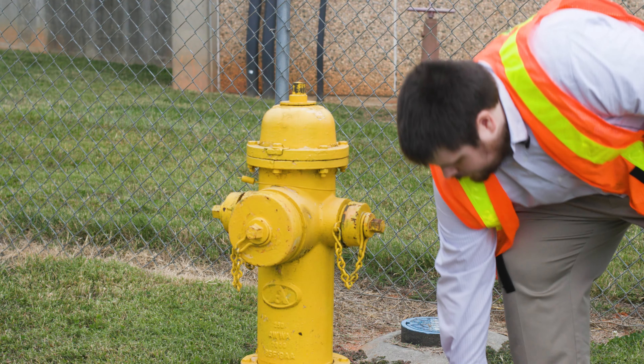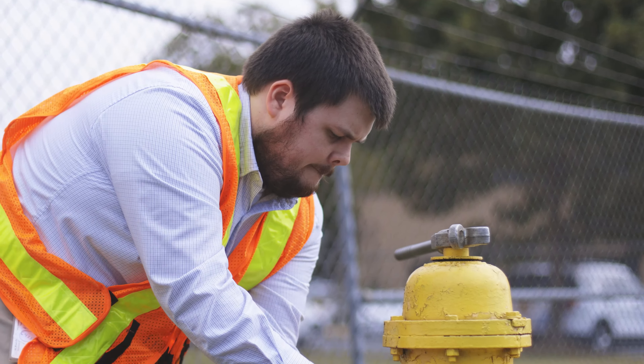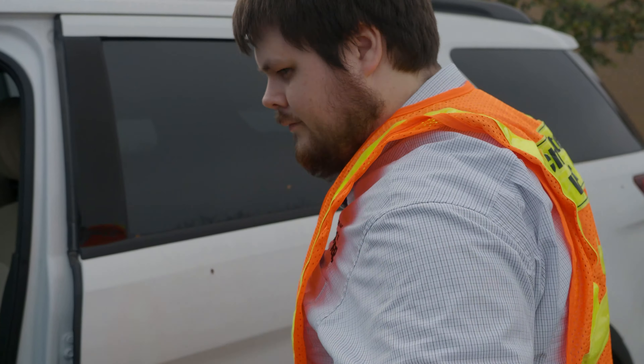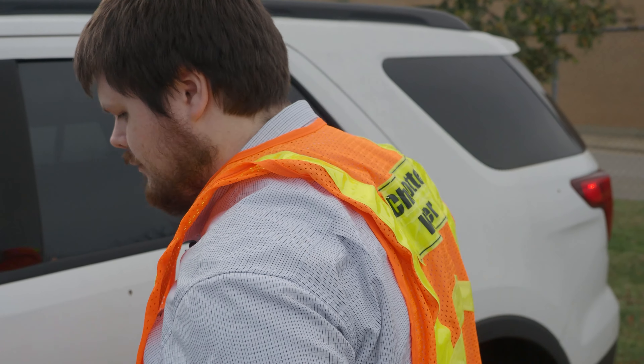This is a typical hydrant that we would install a pressure recorder on. All our pressure recorder is, is a little data logger that we put on a hydrant. It will record pressures continuously and provide a summary for every minute, every hour. We can see what the pressures are doing in our system at specific times of the day, so we can then calibrate our model to them.